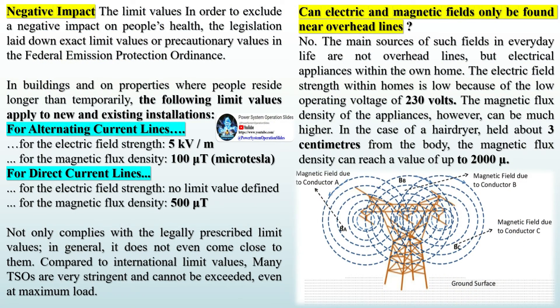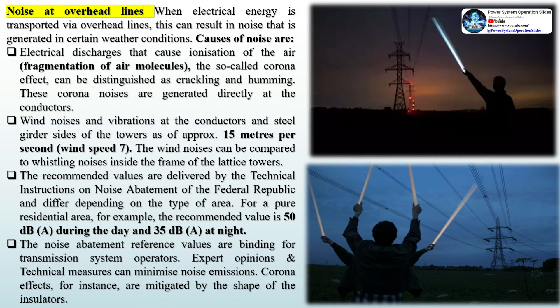Negative impact of transmission lines: in order to exclude a negative impact on people's health, legislation has laid down exact limit values in the Federal Emission Protection Ordinance. In buildings and on properties where people reside longer than temporarily, the following limit values apply to new and existing installations. For alternating current lines, the electric field strength is 5 kV/m and the magnetic flux density is 100 µT. For direct current lines, no limit value is defined for electric field strength, and the magnetic flux density limit is 500 µT.